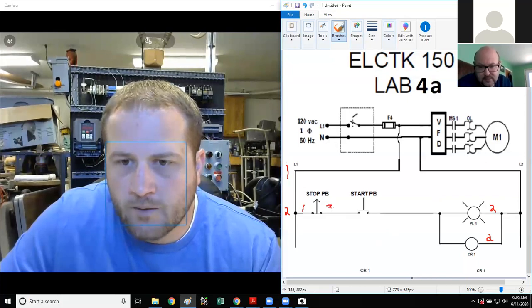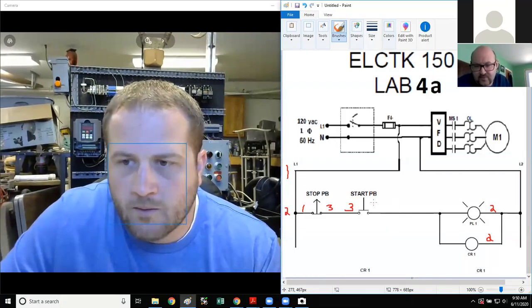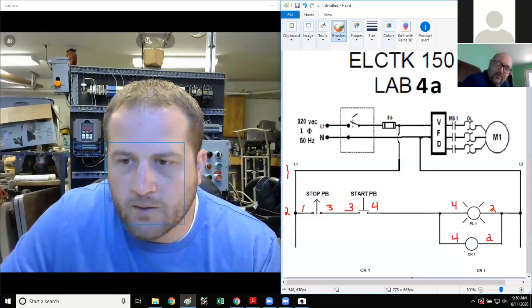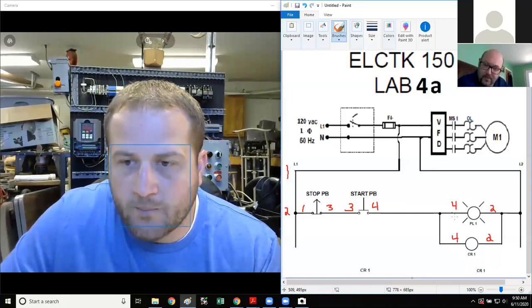Or no? Yep, okay. So that means between push button stop and start push button, that would be wire 3. And then between push button start and light 1 would be 4. And then between control relay and line 4 would be, no, that's connected, so that's line 4 too, right? Yep, they're all on the same potential. So when this gets lit up, this gets energized too.